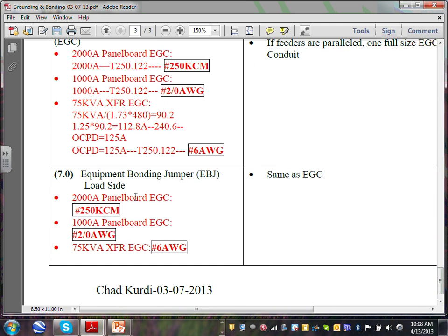If you look at the equipment bonding jumper for the transformer, right here, with the last bullet, it's also number 6. These could be one wire or 2 separate wires. Typically it's one wire, and you lube the 2 sides on the lug nuts and continue with them. Any comments, guys? Any questions about grounding and bonding on the primary side of a transformer for the separately derived system, as well as grounding and bonding on the secondary side? Any comments? Any questions, guys?